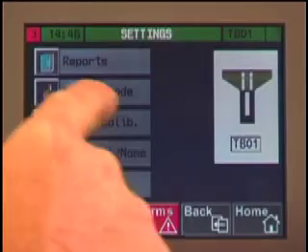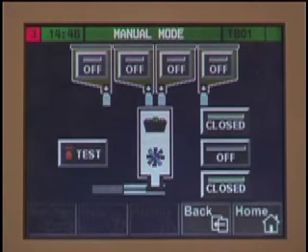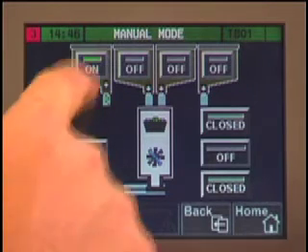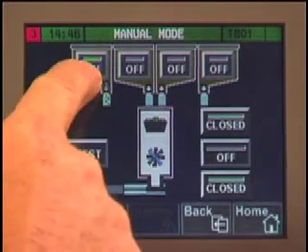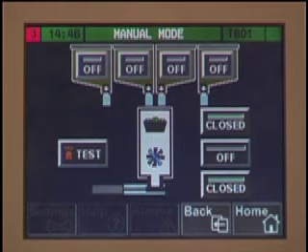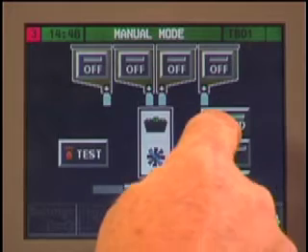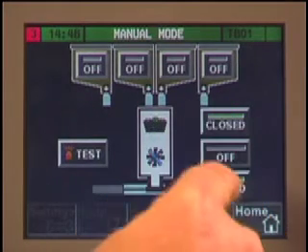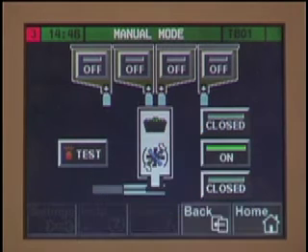The next available setting is manual mode. Under manual mode, you can manually operate material hoppers, the hopper weigh bins, mixers, test alarm beacons, and flow control valves on remote mount models. To check material hoppers, press the off button in sequence to check that the various material hopper valves can be opened and closed. To check weigh bins and mixers, press the first button to open and close the weigh bin, and press the middle button to switch the mixer on and off.